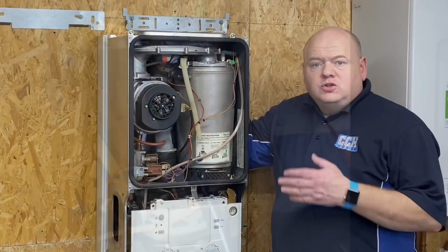So that reading indicates the burner seal has gone, and it's very important if you come to do a service on one of these boilers to check that seal. Almost every one of these I go to now needs the seal changing, so please check that every time you do a service.